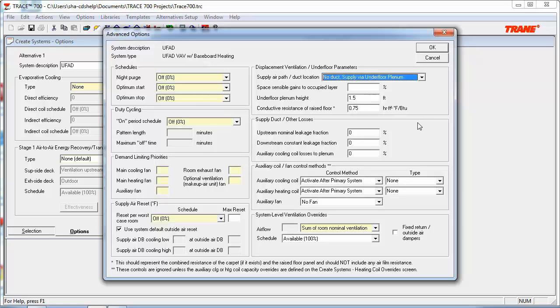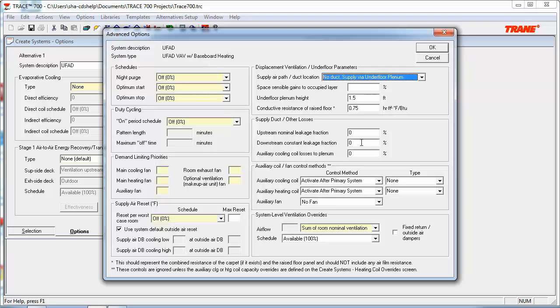Lastly, one more section here in Create Systems I want to focus on is the supply duct slash other losses. Upstream nominal leakage fraction is assumed to bleed into corridor return air path, while the downstream constant leakage is assumed to leak into the occupied layer. This input is typically used for UFAD systems in case you have a leaky underfloor plenum. In addition to all of this, if you want to learn more information about any of these inputs, be sure to press F1 to get additional information.